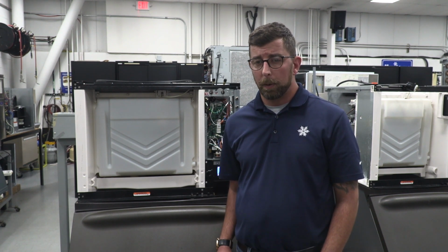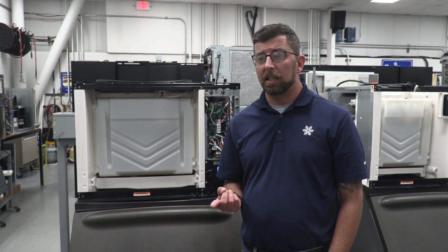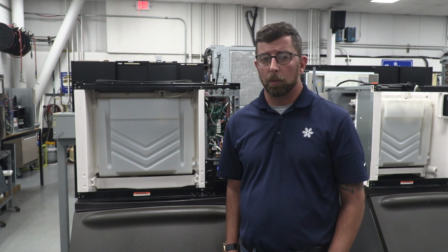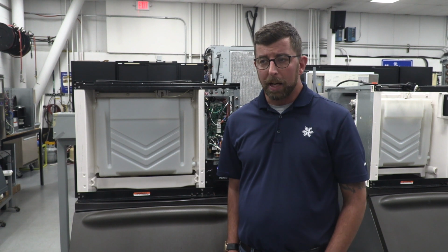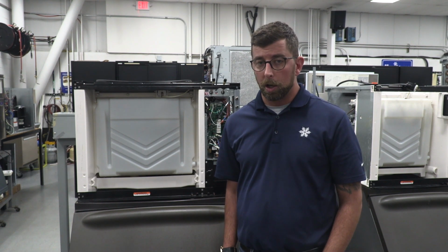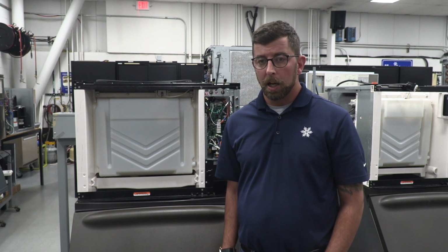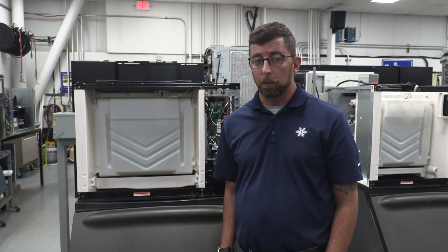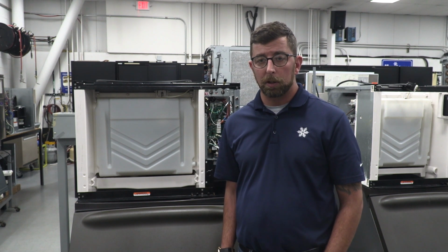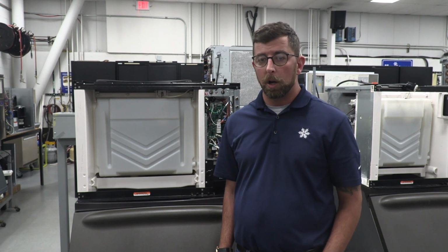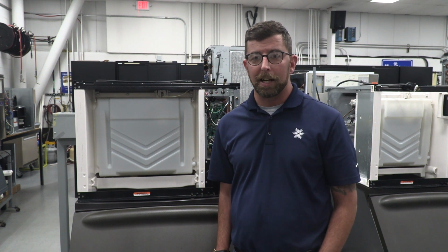But a few things we know here: the water probe was sensing. We're supposed to call for water. If we weren't getting water and it was sensing, we'd be troubleshooting the water probe. But in this instance, we had a water probe telling the board we need water. We had a board calling for water, and we had a valve not providing water. Again, either the water inlet valve itself is our problem or the incoming water supply. Rectify whichever of those two issues is what you have, and you will be back to putting water in the trough, pumping water over the plate, making and harvesting your ice.